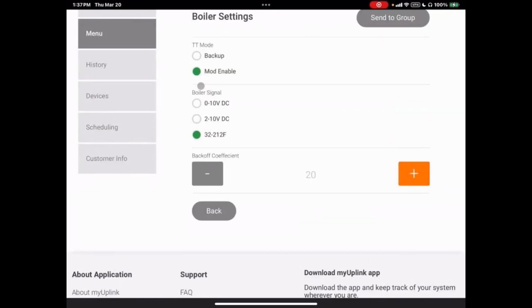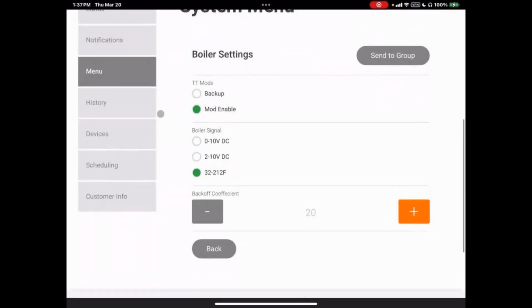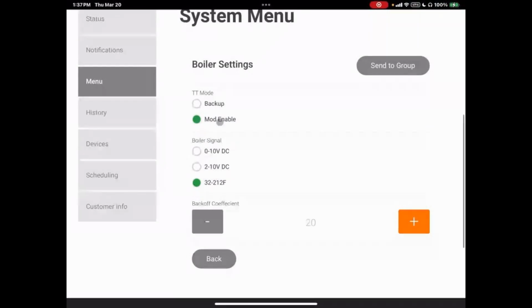And because this is a dual fuel, we have the boiler settings. Here we've got modulation enabled, so our TT mode. Then we have three different settings. We can send a 0 to 10 DC signal, a 2 to 10 DC signal, or this third setting that is 32 to 212. A couple of boiler manufacturers utilize a fixed modulating scale that is 0 to 100 degrees Celsius, so that's why we've listed this as 32 to 212. Mainly this is Viessmann, but this is the setting you would choose for that type of boiler.